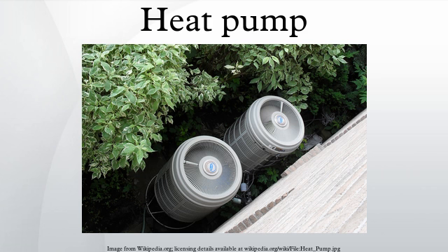Heat sources and sinks. A common source or sink for heat in smaller installations is the outside air, as used by an air source heat pump. A fan is needed to improve heat exchange efficiency. Larger installations handling more heat, or in tight physical spaces, often use water source heat pumps. The heat is sourced or ejected in water flow, which can carry much larger amounts of heat through a given pipe or duct cross-section than airflow can carry.